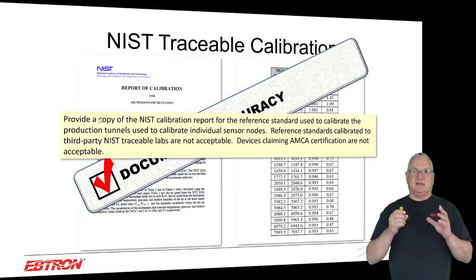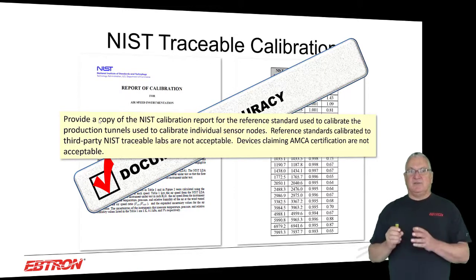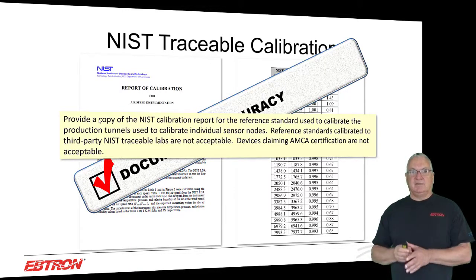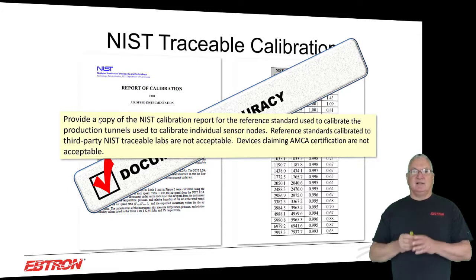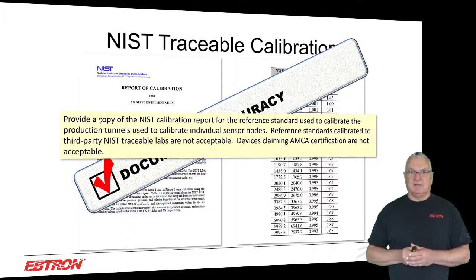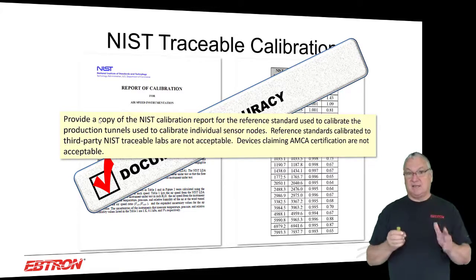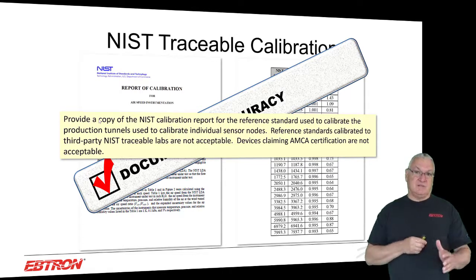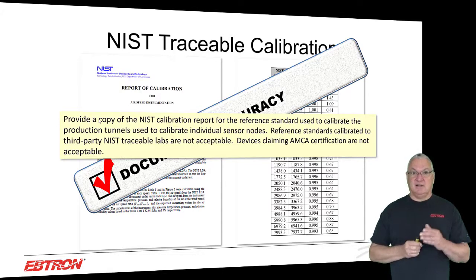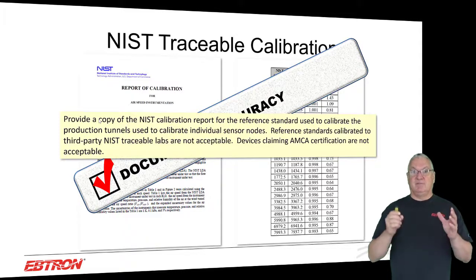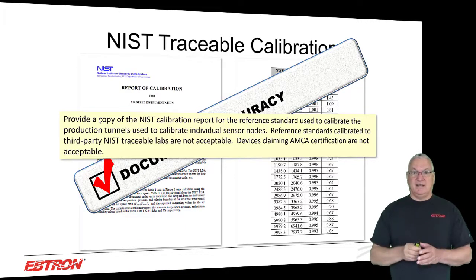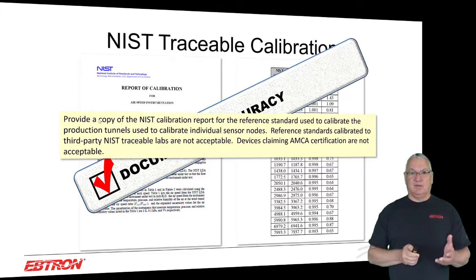And the only thing I'll say about the AMCA stuff is you can certify one flow meter in an AMCA certified tunnel and then make claims that the rest of your product line is AMCA certified. So you'll see people say that they've tested them or whatever with the AMCA stuff, but honestly they're not calibrating and testing each individual unit. They're simply making one work very well, calibrate it, test it, create a report, say I'm AMCA certified. A little bit different than what we do.